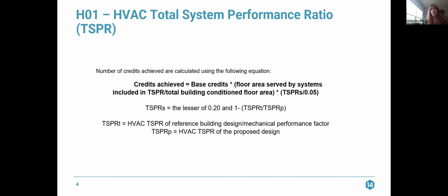But for the sake of section C406, the way that you calculate the number of credits is based on the outcomes of the model that you create. And this is a very simplified model, but what we would look at, your credits achieved would be equal to the base credits allowed in the tables in section C406, multiplied by the floor area served by the systems included in the TSPR. So if only 40% of your building can use the TSPR method, you could achieve these credits for that 40% of your floor area. So the ratio of that floor area times TSPRS divided by 0.05.